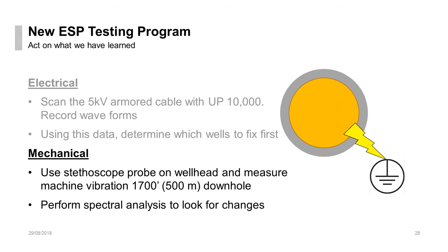And then the other thing that we started doing, this is very ESP specific, is using a stethoscope probe on the wellhead, and we can measure the machine vibration that's 1,700 feet downhole. I liken this to a 60,000 pound guitar string, and we're just standing at one end of it listening.